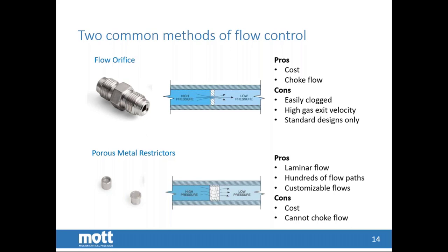I would like to emphasize the multi-flow path of the porous over the orifice, which is the one path. If you get particulate that hits that orifice, it plugs the orifice and immediately impacts your flow. With the porous metal restrictor, you have hundreds of flow paths, so if you get that one particulate that comes to the surface of the porous, it's not going to impact your flow. Over time, if enough particles build up, it will start to slow your flow down, but it will be a gradual decrease — it won't be an instant off.